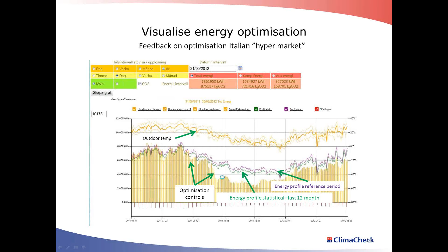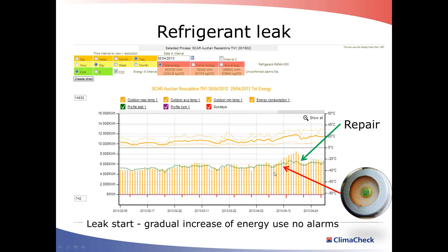You can also detect things like refrigerant leakage, where you can detect deviation from the expected consumption. When it starts increasing, you can send somebody out and fix it rather than continue running for a long period and have the problem when you get the hot day.